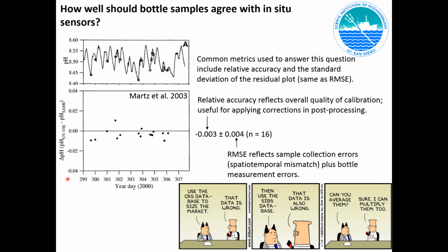So the relative accuracy value is going to tell you something about the overall quality of your calibration, and you could imagine applying a simple offset to that value in order to bring a sensor into agreement with your bottle samples. There's another really important number here, though, the standard deviation of the residual. This reflects how well you're doing in terms of your spatiotemporal mismatch or added in bottle measurement errors. We typically assume that our bottle measurement errors are relatively small compared to the spatiotemporal mismatch issue. So in this case, we were achieving a standard deviation in the residual, the RMSE is the same, calculated the same way, of 0.004 pH.